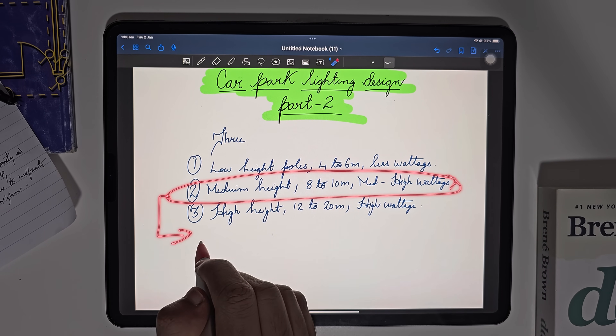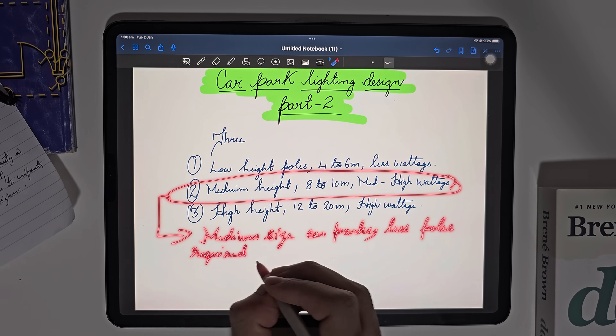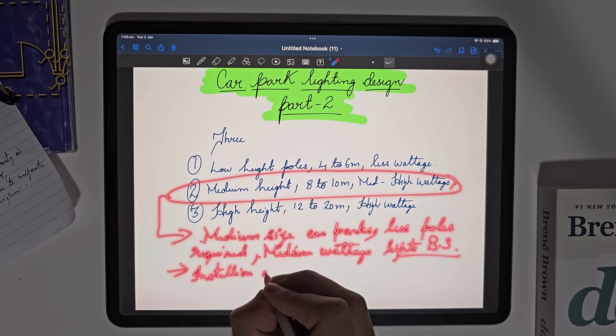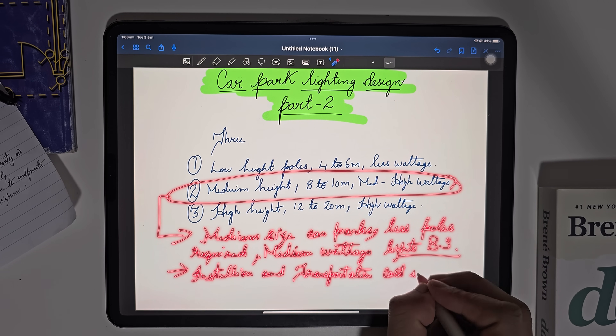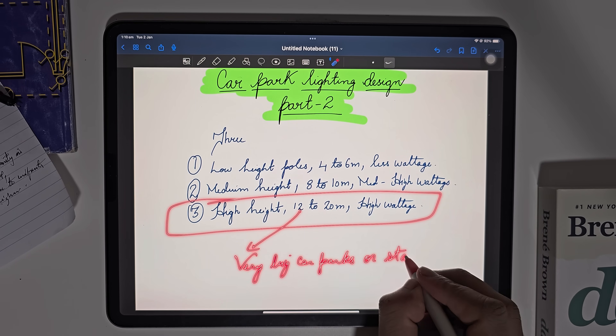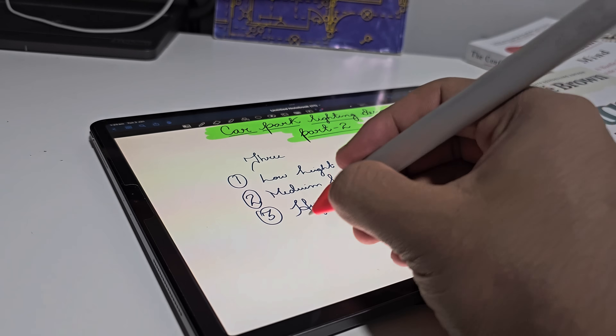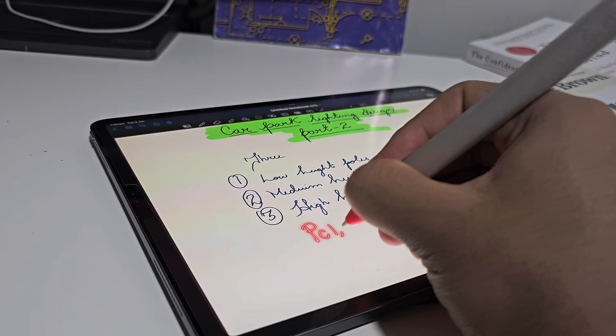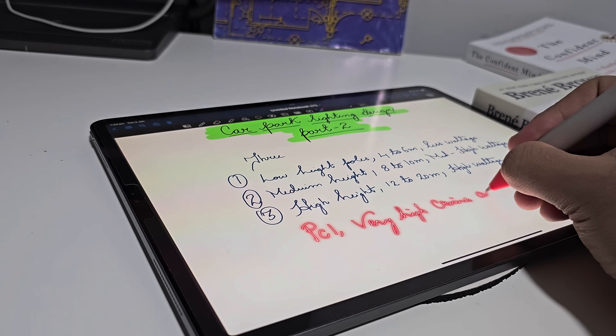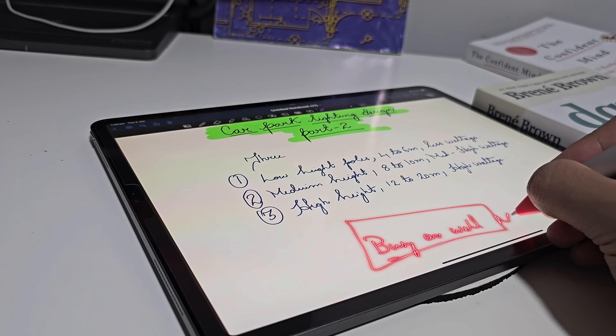Meanwhile, medium size poles can be used in medium and large size car parks where fewer poles are required. Installation and transportation of poles are simple and cost effective in this method. The third type is a tall height pole of around 12 to 20 meters where a high wattage light fitting is usually used, suitable for very big car parks and stadiums where very few poles — around 4 — are required. Out of these three types, I will use the medium height poles of 8 meters as this car park is big. We will also consider this car park as a PC1 category with high crime and it is in a busy area.